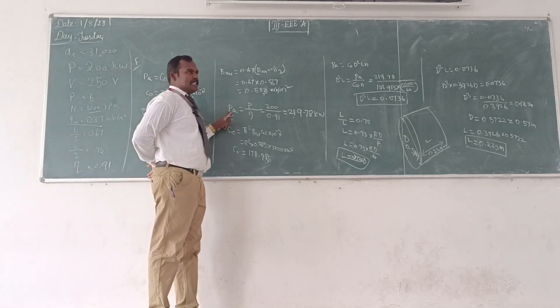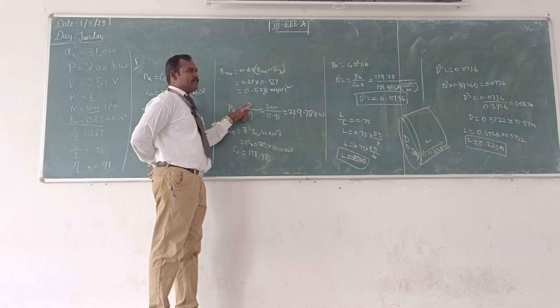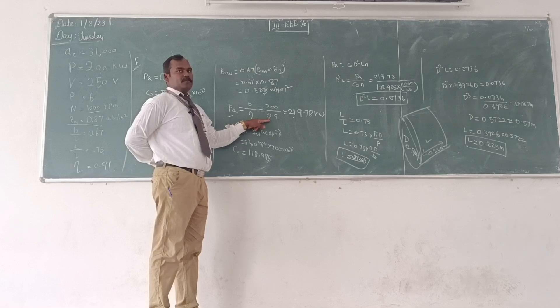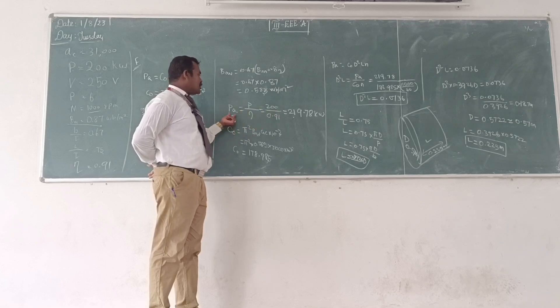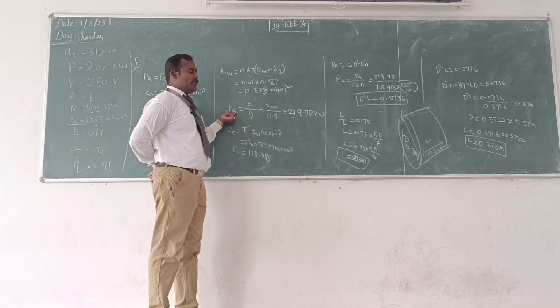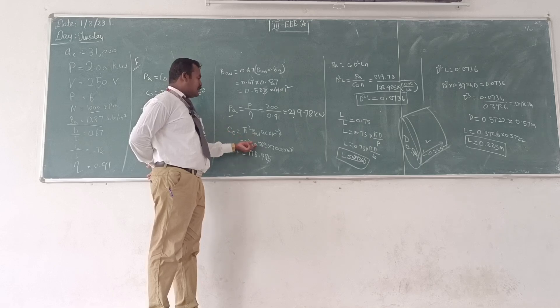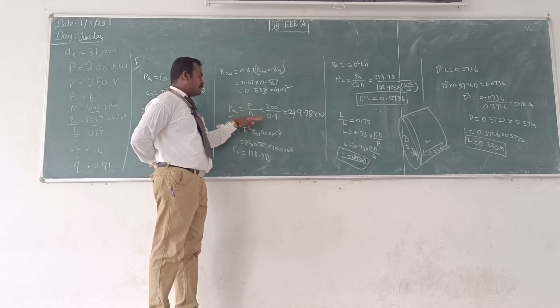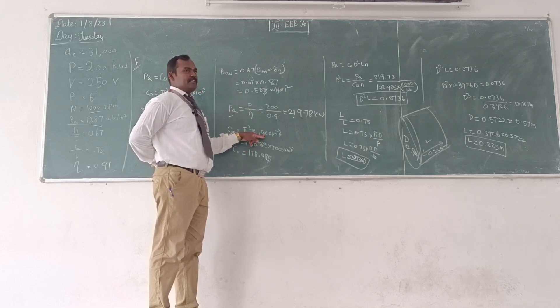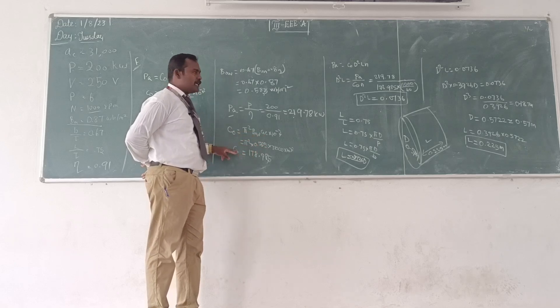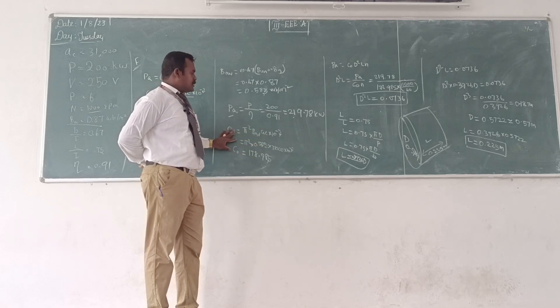Since it is a generator, the power developed in the armature PA should be equal to P divided by efficiency. The P value is given, and the efficiency is also given as 91%. From that we can calculate the PA value. Similarly, we have the formula for the output coefficient C0. The BAV value has been obtained and the AC — ampere conductors — is given as 31,000. So we can observe all values and find the output coefficient.